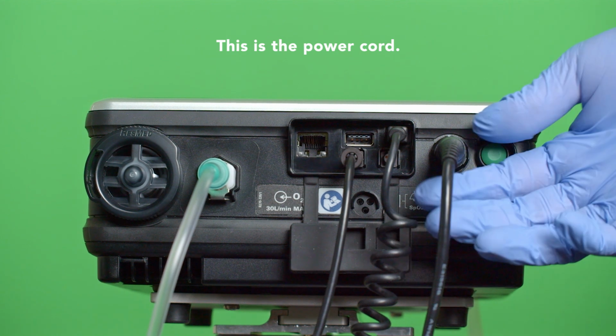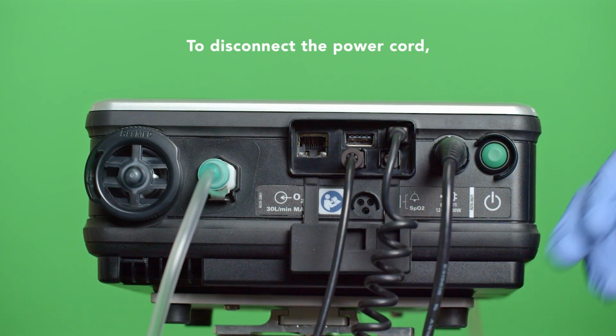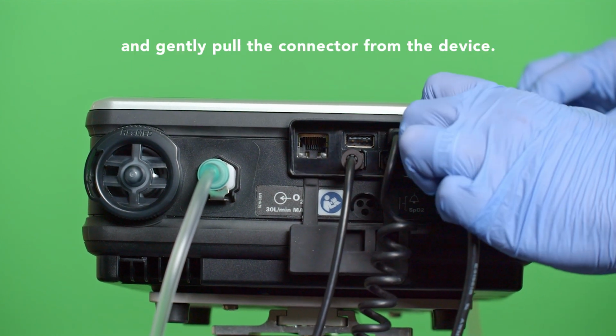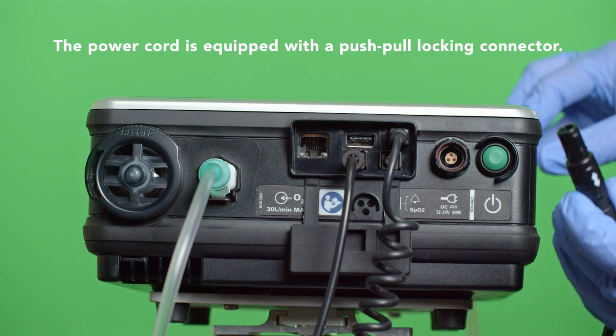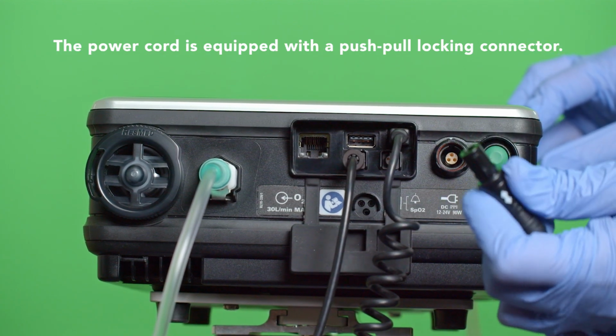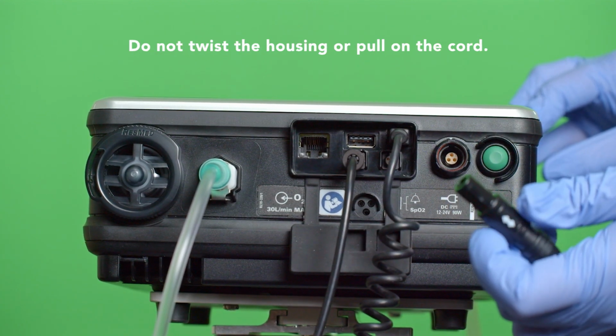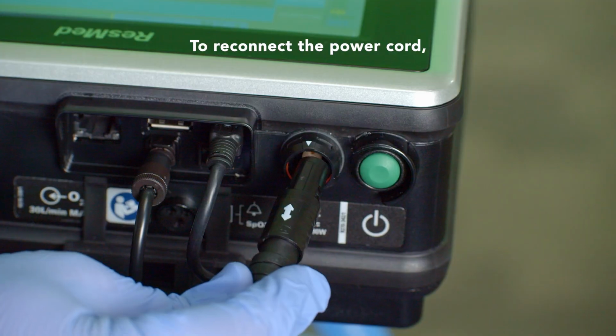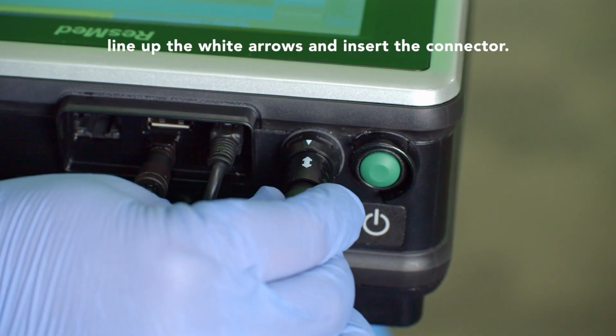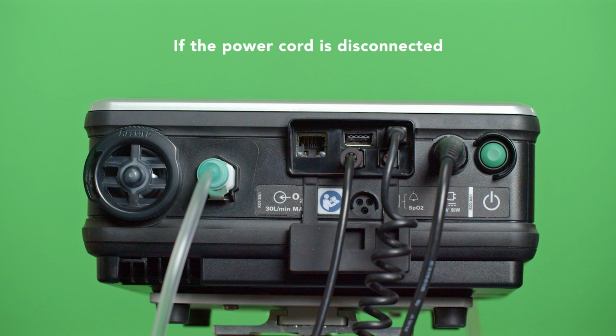This is the power cord. To disconnect the power cord, hold the power cord housing and gently pull the connector from the device. The power cord is equipped with a push-pull locking connector. Do not twist the housing or pull on the cord. To reconnect the power cord, line up the white arrows and insert the connector. If the power cord is disconnected or if the Astral is not plugged in, the internal battery will last approximately 8 hours.